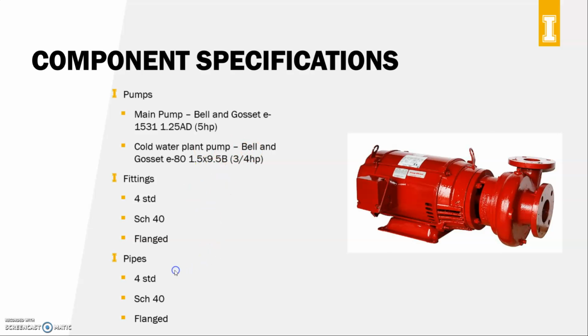Now, for our piping system, we chose 4-inch nominal standard piping, and the reason we did this was because inside of our piping system, inside the steam tunnels, there's a limited amount of space, and it's stated in the write-up that in order for us to operate in the steam tunnels, we have to have 2 inches of insulation around our pipe. And for that reason, 2 inches of insulation on a 4 nominal pipe brings it out to approximately 8 inches in diameter, and that's about the limit to the space that we can fit inside of the steam tunnel. And so we decided that this was the largest pipe size that we could choose that would meet our water flow, but would also fit inside of the steam tunnel with that insulation requirement.